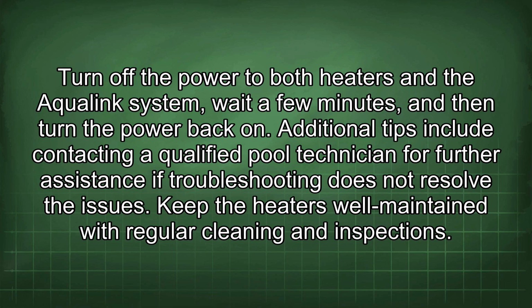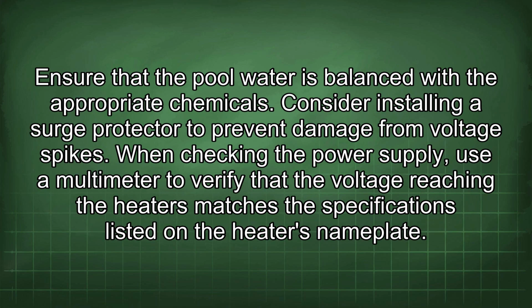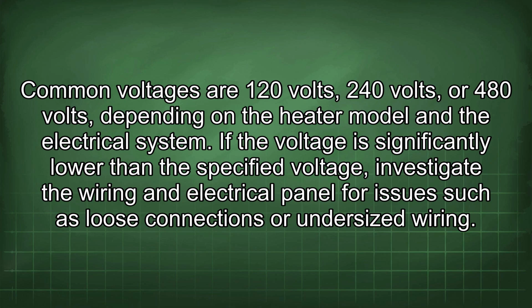Keep the heaters well maintained with regular cleaning and inspections. Ensure that the pool water is balanced with the appropriate chemicals. Consider installing a surge protector to prevent damage from voltage spikes. When checking the power supply, use the multimeter to verify that the voltage reaching the heaters matches the specifications listed on the heater's nameplate. Common voltages are 120 volts, 240 volts, or 480 volts, depending on the heater model and the electrical system. If the voltage is significantly lower than the specified voltage, investigate the wiring and electrical panel for issues such as loose connections or undersized wiring.